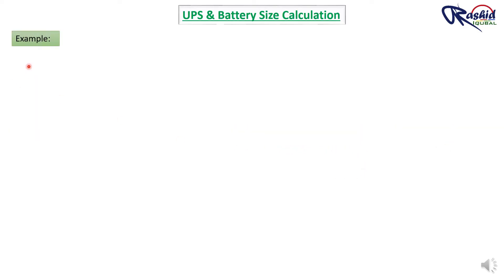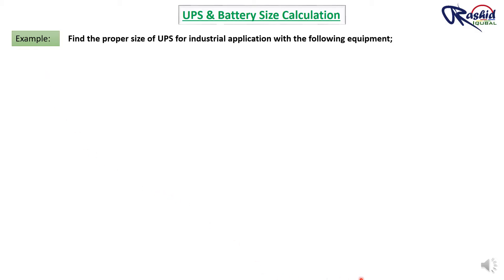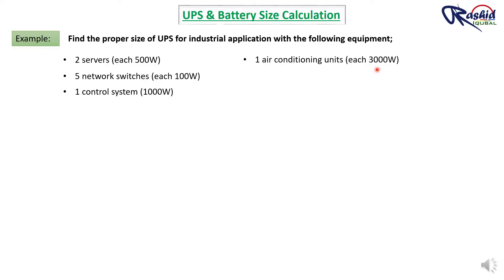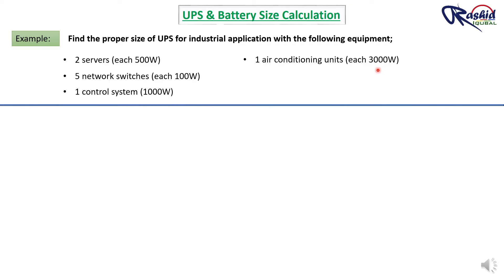Let me take one example to help you understand better. Find the proper size of UPS for an industrial application with the following equipment: two servers each consuming 500 Watts, five network switches each at 100 Watts, one control system at 1000 Watts, and one air conditioning unit at 3000 Watts.